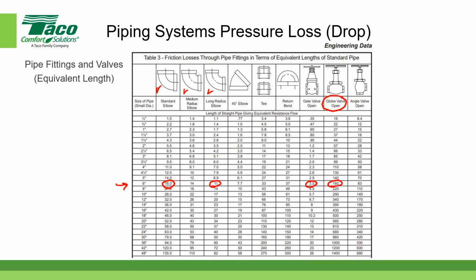So when you decide the components that you want to use in your system, you have to keep in mind what the equivalent length is of the different components. A full port ball valve, for example, has a very, very low pressure drop, even less than a gate valve, probably around, say, 1 foot per 100 feet or something in that order of magnitude. So hopefully you get the general idea that when we talk about fittings, we're talking about equivalent length of straight pipe.